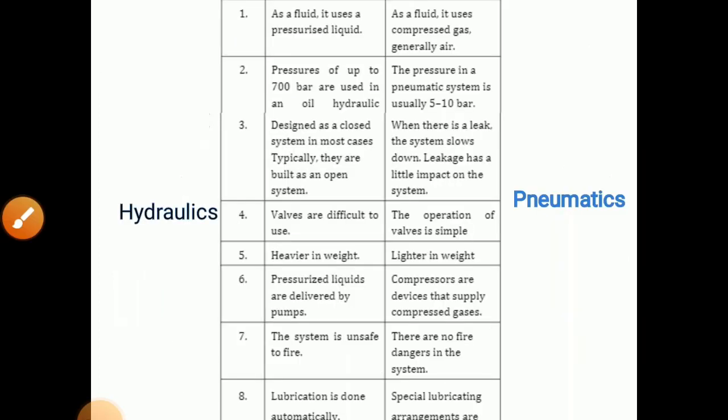So there is some difference between pneumatics and hydraulics. As a fluid, hydraulics uses pressurized liquid while pneumatics uses compressed air. Now second comparison, pressures of up to 700 bar are used in oil hydraulics, but in pneumatic system we can use up to very small 5 to 10 bars.